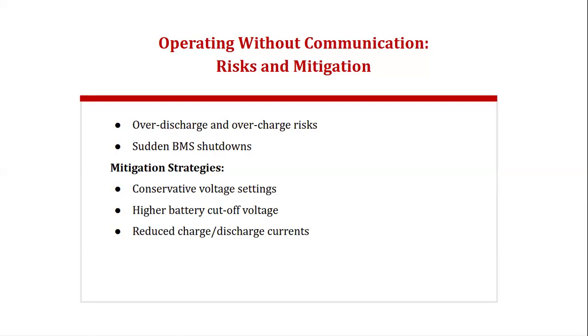I mentioned that there are some batteries that don't even have communication ports, yet they are lithium-ion batteries and they are in use. It's just that they have their limitation. Now, what do you do if you happen to connect to batteries that do not have communication, or the inverter is not really supporting it fully? Maybe it doesn't have communication ports for lithium-ion battery, but to be economical, and probably before the clients agree to change it to a modern type that can do that, you can still manage it, you can still use it. It's not that it's not going to work. The only thing that will happen is that the range of operation on the battery will be narrowed down. That's when you properly adjust or program the inverter, which is the mitigation strategies that we're talking about.